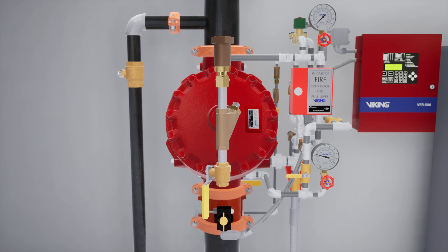The prime line directs water to the prime chamber of the Deluge Valve. The prime line consists of an open priming ball valve, a Y strainer, a restricted orifice, and a check valve.